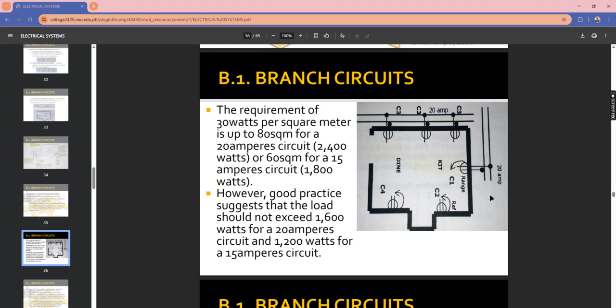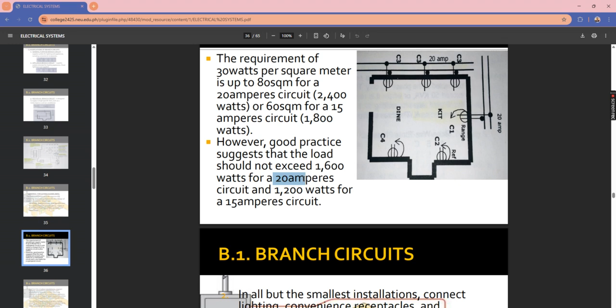Because if it exceeds that, say you reach 17 or 18 outlets and the breaker you used is only 20 amperes, it will probably exceed the load of your circuit line. So if you really want 16 on one line, you need to increase your amperage - you can make it 30 or 50.